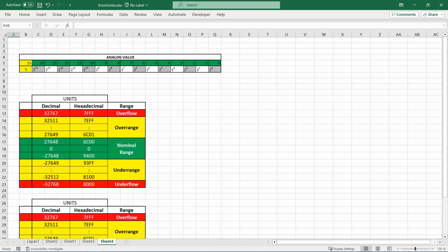As you know, CPU can process information only in digital format, so analog value is therefore converted into a bit pattern. This bit pattern is held in the 16-bit memory area of type integer. Bit number 15 contains the sign of the value. Bits between 0 and 14 contain value.